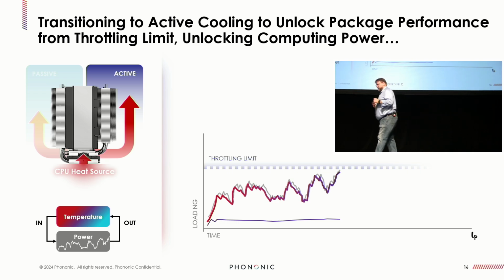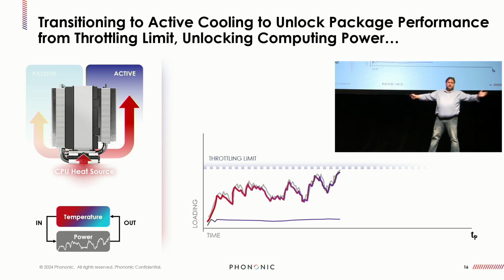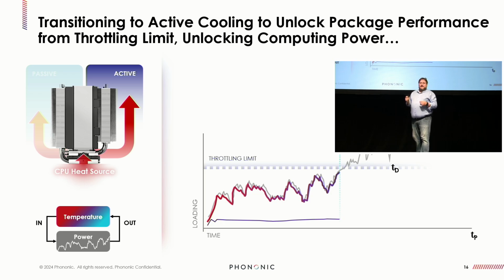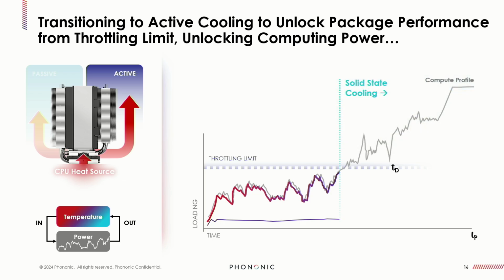But what if we can combine this passive cooling technique below the throttling limit, no additional power consumption. But once we reach this throttling limit, we decouple the case temperature, the die temperature, and we allow that compute load to continue to increase while we actually reduce the temperature or the thermal profile of the processor.